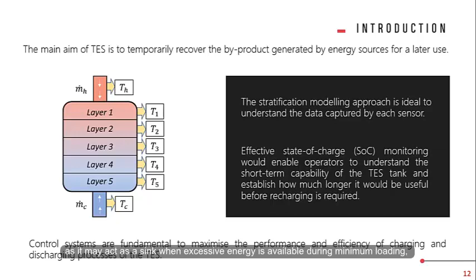As I mentioned before, control systems are fundamental to maximize the performance and efficiency of charging and discharging processes of the thermal energy storage. Given that the location of temperature sensors is usually alongside the tank's height, the stratification modeling approach is ideal to understand the data captured by each sensor. However, knowledge of the state of charge, rather than the temperature information only, is necessary for the effective energy management of the thermal energy storage. Effective state of charge monitoring will enable operators to understand the short-term capability of the thermal energy storage tank and establish how much longer it will be useful before recharging is required.